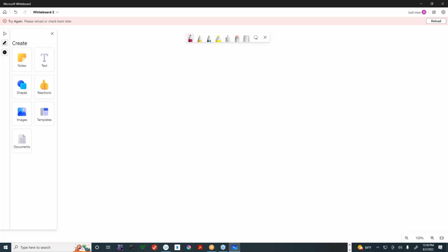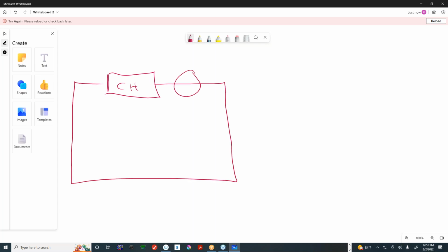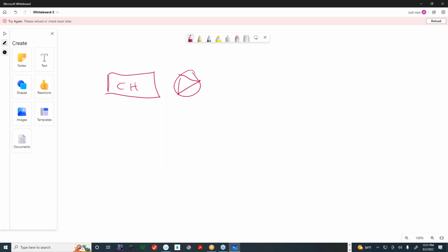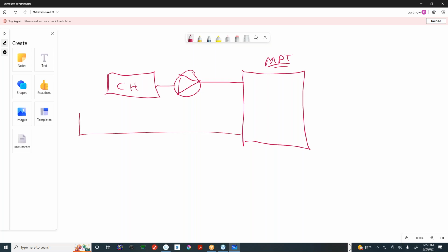Yes, it adds volume. So let's say you had, again, a chiller and a primary circuit like this. Let's put a circulating pump in there. And then this is the secondary circuit. So one possibility is to put in your multi-purpose tank. And now you have a primary circuit on the left side, and on the right side the secondary circuit. And there's our load again, like we had before.